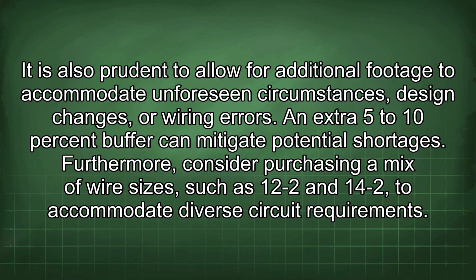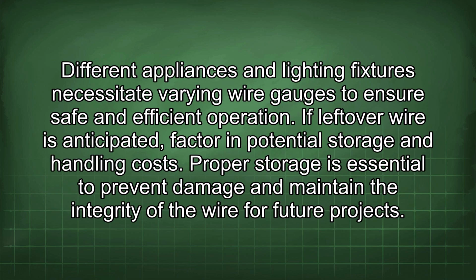It is also prudent to allow for additional footage to accommodate unforeseen circumstances, design changes, or wiring errors. An extra 5 to 10% buffer can mitigate potential shortages. Furthermore, consider purchasing a mix of wire sizes, such as 12-2 and 14-2, to accommodate diverse circuit requirements. Different appliances and lighting fixtures necessitate varying wire gauges to ensure safe and efficient operation. If leftover wire is anticipated, factor in potential storage and handling costs. Proper storage is essential to prevent damage and maintain the integrity of the wire for future projects.